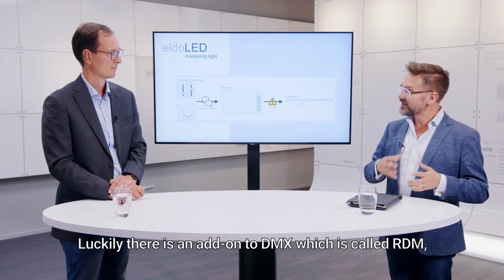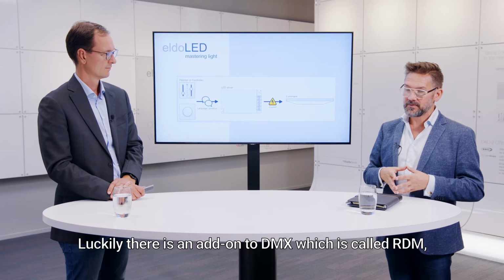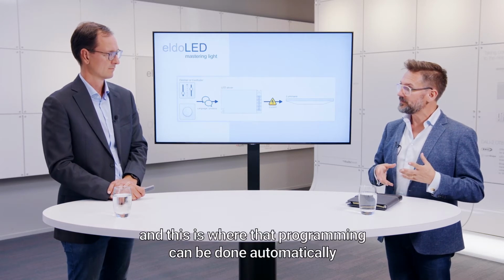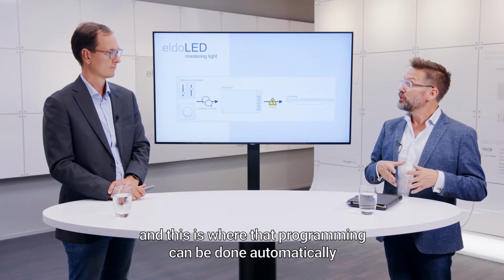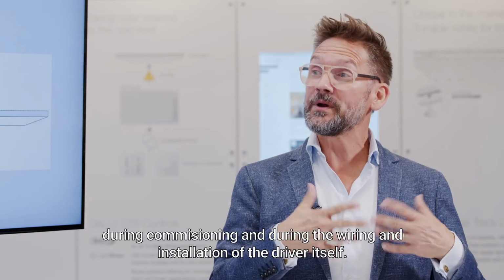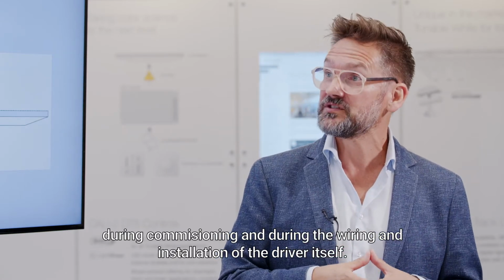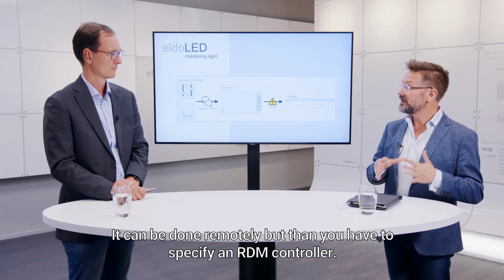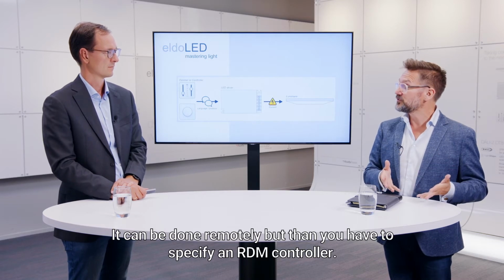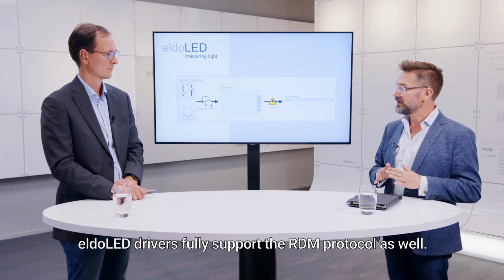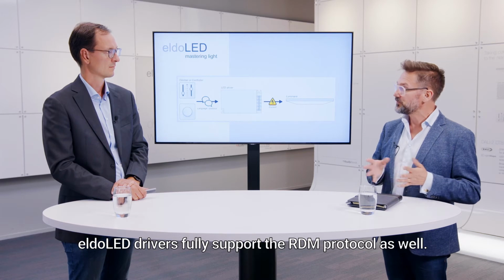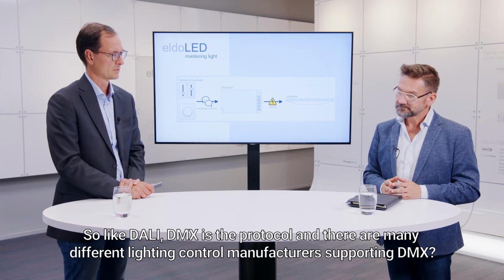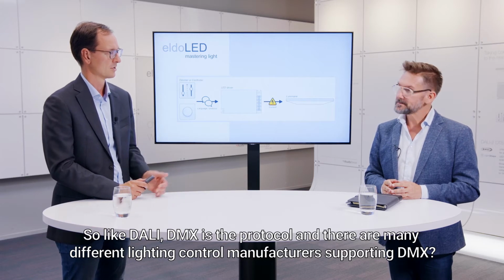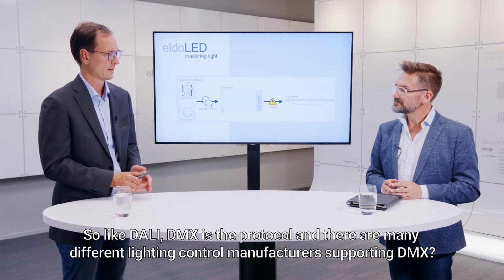Luckily, there is an add-on to DMX, which is called RDM. And this is where that programming can actually be done automatically during commissioning and during the wiring and installation of the driver itself. It can be done remotely, but then you have to specify an RDM controller. eldoLED drivers are fully RDM, they fully support the RDM protocol as well. Okay. In that area. So same as with DALI, DMX is the protocol.